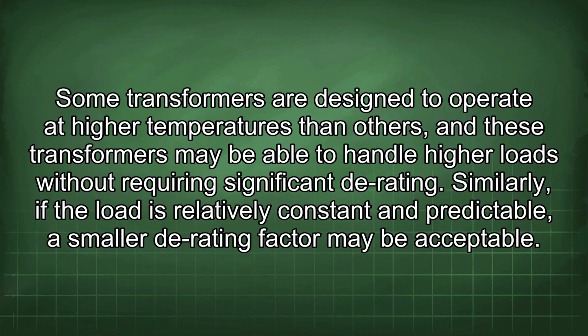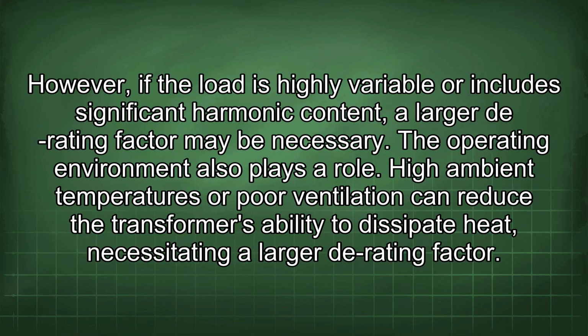Some transformers are designed to operate at higher temperatures than others, and these transformers may be able to handle higher loads without requiring significant derating. Similarly, if the load is relatively constant and predictable, a smaller derating factor may be acceptable. However, if the load is highly variable or includes significant harmonic content, a larger derating factor may be necessary. The operating environment also plays a role. High ambient temperatures or poor ventilation can reduce the transformer's ability to dissipate heat, necessitating a larger derating factor.